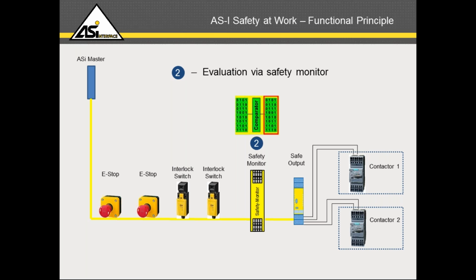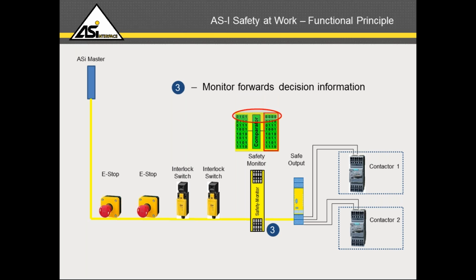So the safety monitor, as I said a moment ago, has been parameterized using this ASIMON software, and during network commissioning, the safety monitor has learned all of the code sequences for each of the connected safety slaves. Once it's in operation, the safety monitor constantly is comparing the received codes from each device against the expected codes. If at any time a received code sequence is not what's expected by the safety monitor, a decision is made in the safety monitor as per its parameterization, and the safety monitor forwards its decision to the safe output device.